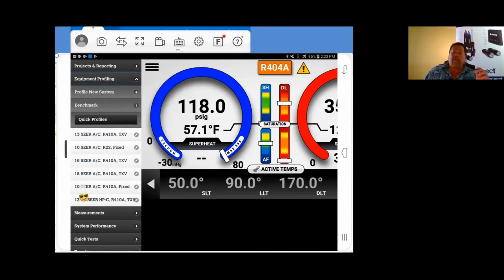We just made that profile a second ago. You can make as many profiles as you want, but in all actuality, it'll only take about 8 different profiles to do business as usual. You've got R22, 410A, different efficiencies like 13 to 16 SEER, 12 SEER, 10 SEER units, and different metering devices. So you'll have maybe 8 profiles, and then selecting your tonnage is the only other thing you need to do.